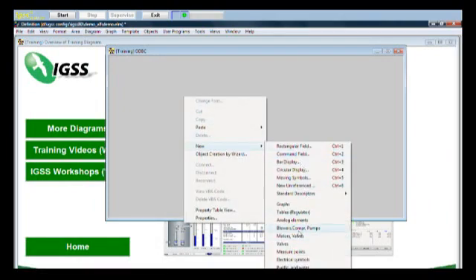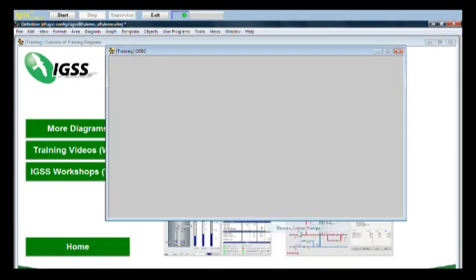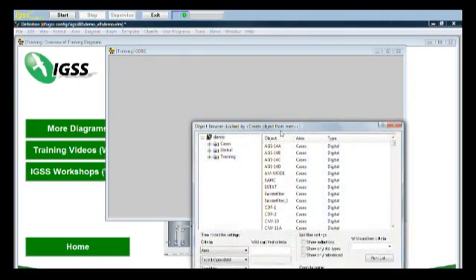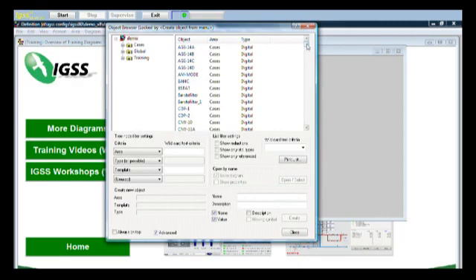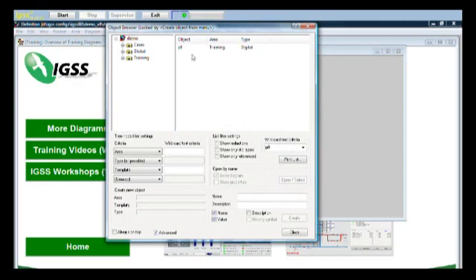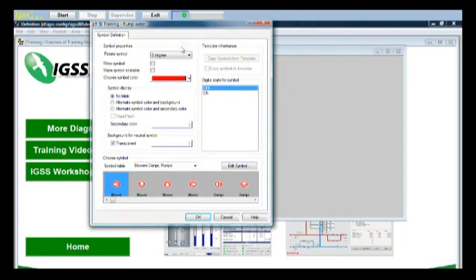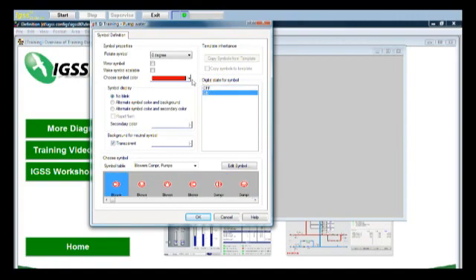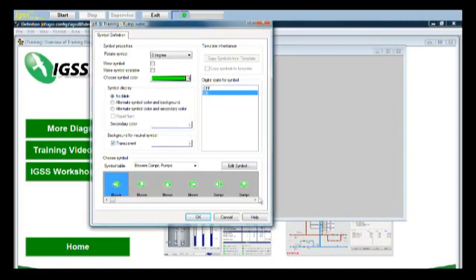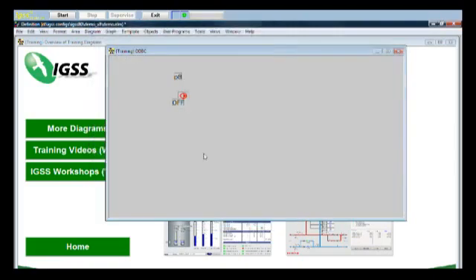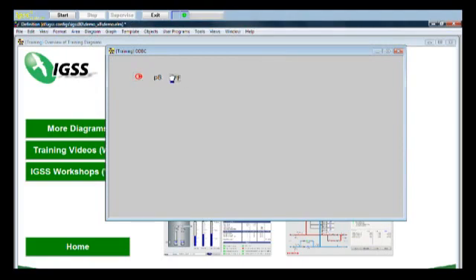We click on the ODBC diagram and now we can import the object we created. Right click, new, and we created a pump. So we'll go to the blowers, compressors and pumps table, select it, and bring up the object browser. We want a new object. That object is called P8. There it is, there's our new object. Double click it and we choose the symbol. Let's choose red for off and green for on. That's it. You have created a diagram and an object using the ODBC interface.